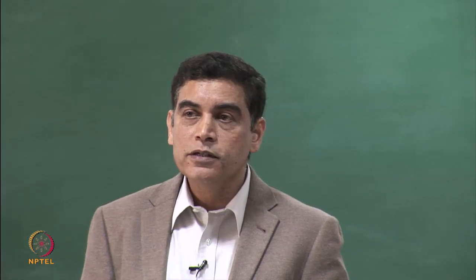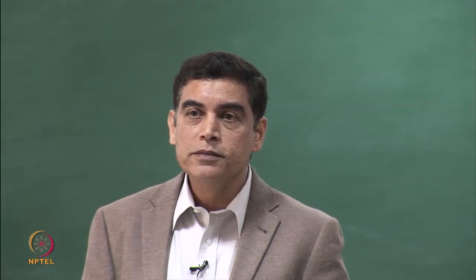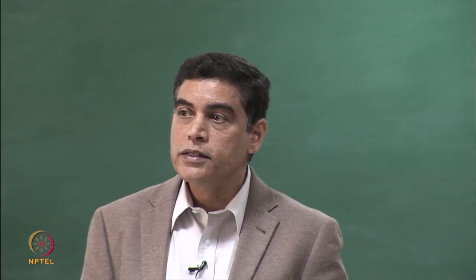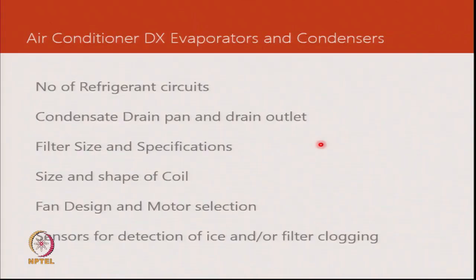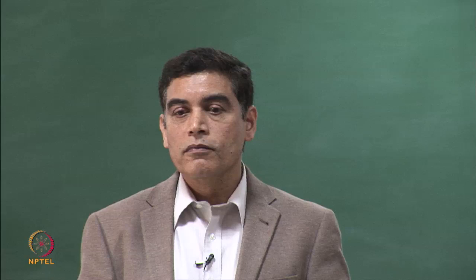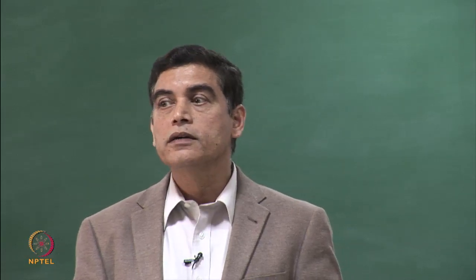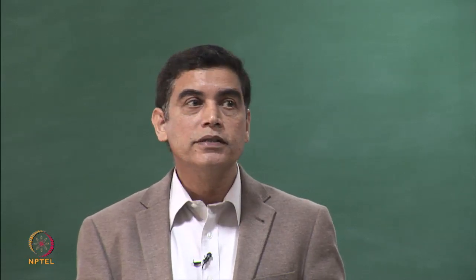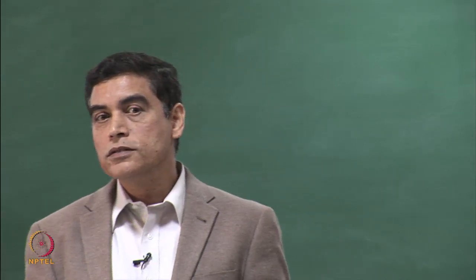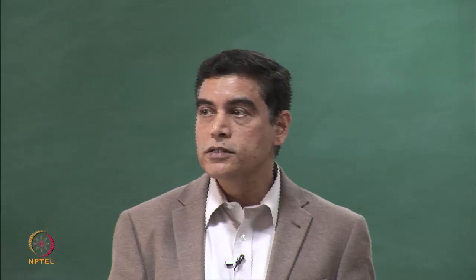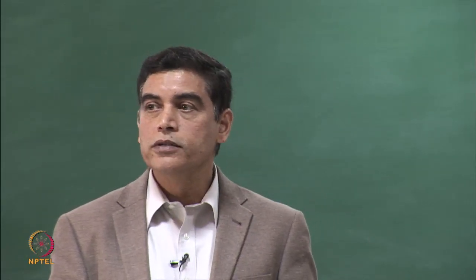One design solution is to keep the face velocity on the coil in the region of 2.5 metres per second to ensure there is no condensate carryover. The angle at which the coil is positioned also determines how well condensate flows into the drain pan. In cassette-type units installed in the ceiling, draining condensate is challenging and pumps are typically installed — a condensate drain pump coupled to a sensor ensures all moisture is expelled into a drain.